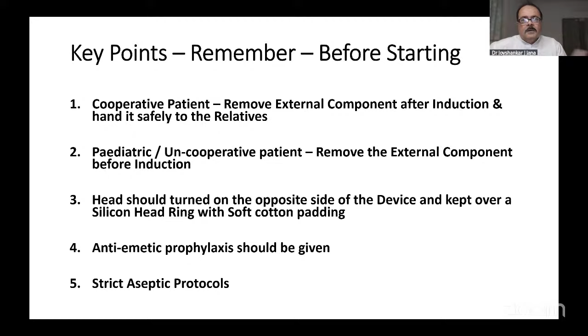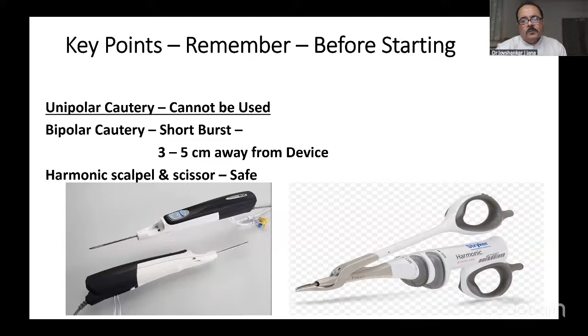So unipolar cautery, as Pradeep sir has already mentioned, cannot be used. Bipolar cautery can be used, but in short bursts. The bipolar cautery should be used at least 3 to 5 centimeters away from the device. It has to be very much away from the device. And if you're having head and neck surgery, or surgery near the head where the device is very close to your incision, then its use is also quite dangerous. Safest is the harmonic scalpel. We know an ultrasonic energy source is used where there is no electric current. So harmonic scalpels and scissors are very safe to use.